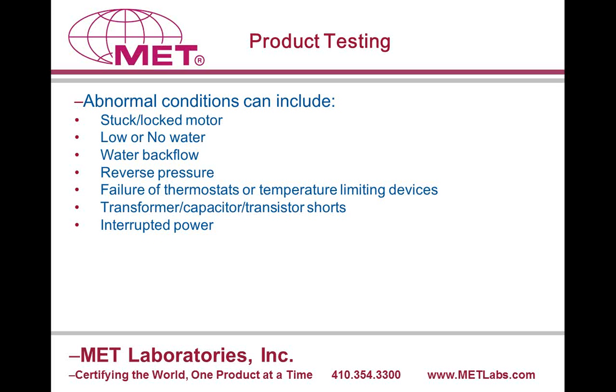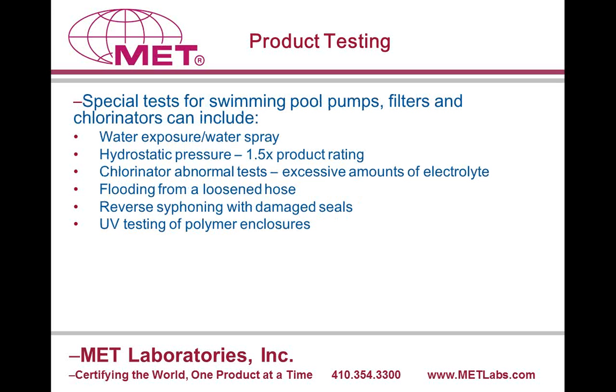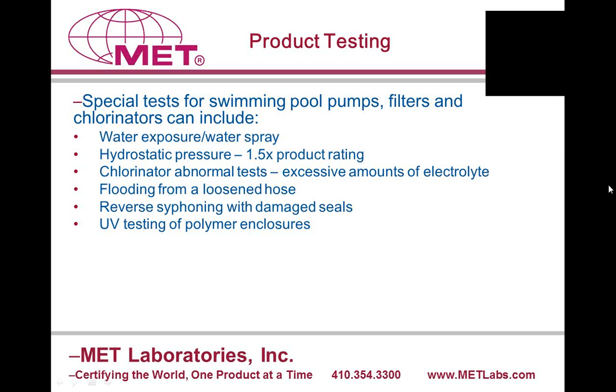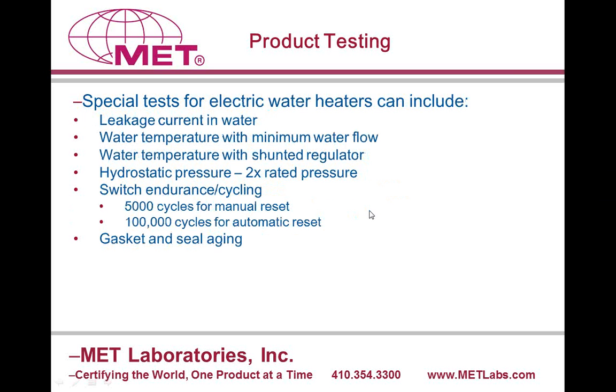Here are some of the abnormal conditions that we're going to look at. We only do one fault at a time, and we see what happens. We want to make sure that we don't have excess heat, fire, or shock. Now, in each standard, there are special tests that will be done on the equipment to make sure it's safe. For example, if we have swimming pool pumps, filters, chlorinators, we're going to look at water exposure. We're going to look at excess electrolytes in the chlorinator. We're going to look at the possibility of flooding. We're going to look at some UV exposure if you have a polymer enclosure.